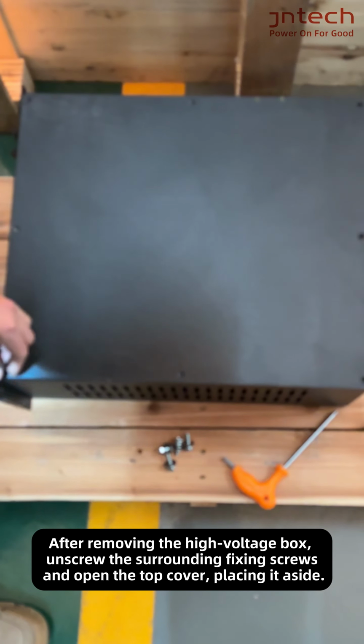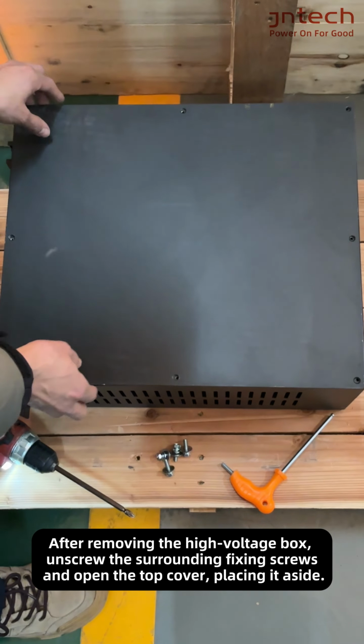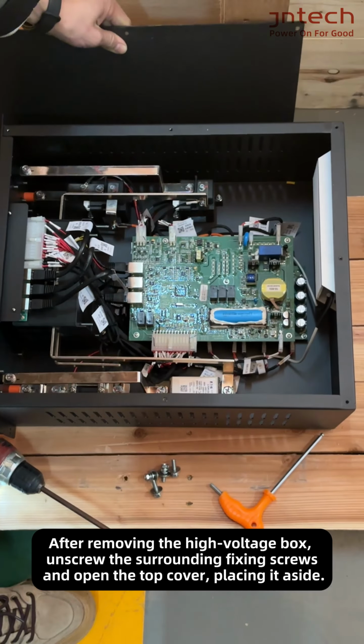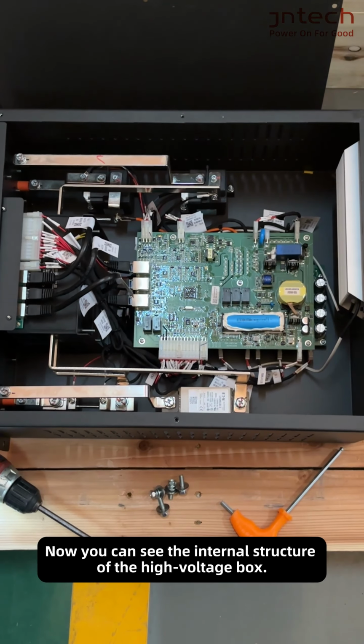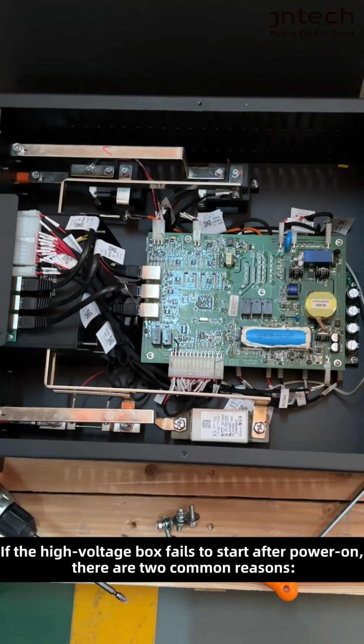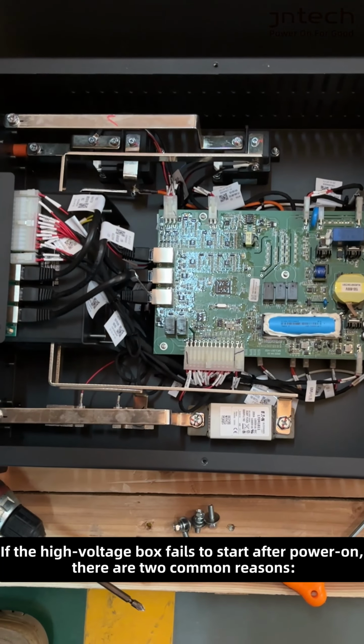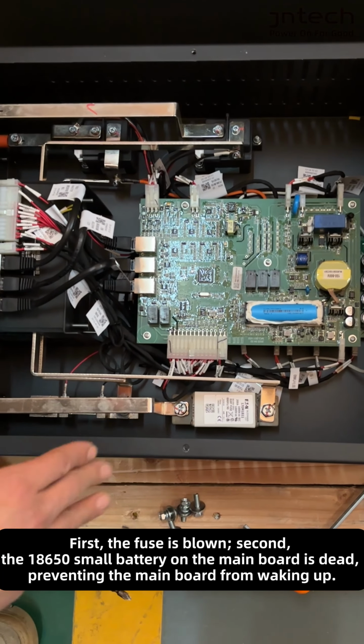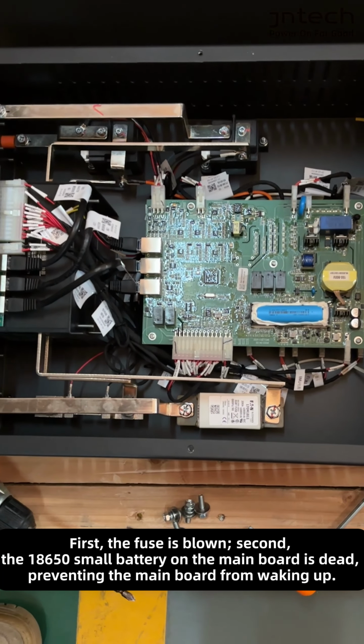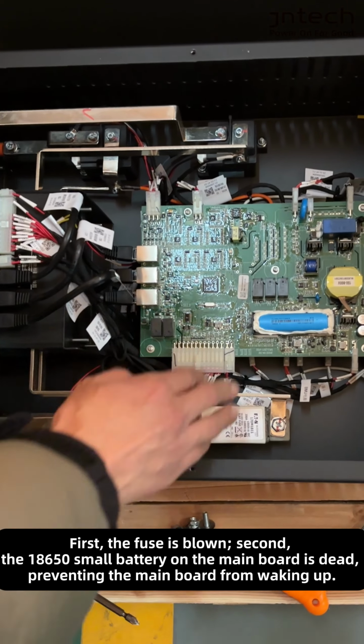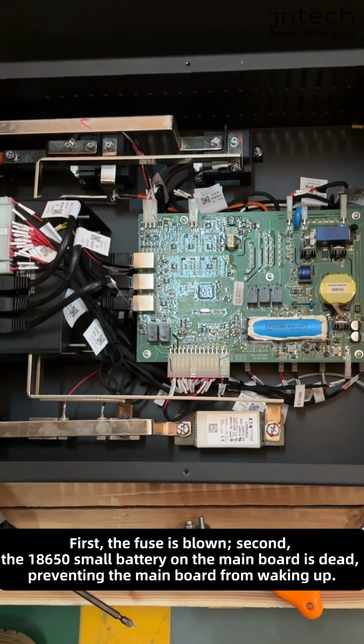After removing the high voltage box, unscrew the surrounding fixing screws and open the top cover, placing it aside. Now you can see the internal structure of the high voltage box. If the high voltage box fails to start after power on, there are 2 common reasons. First, the fuse is blown. Second, the 18650 small battery on the main board is dead, preventing the main board from waking up.